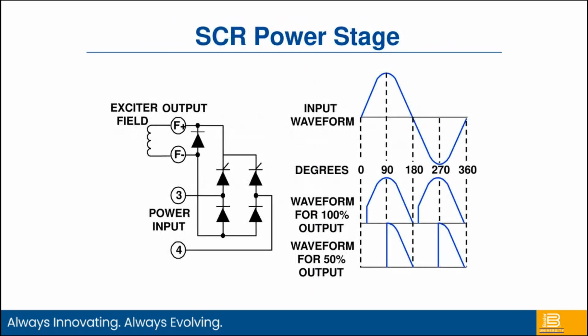So with that, I brought up a point there of power stages. The voltage regulator is monitoring the output of the generator, very much like the cruise control on your car does with speed, except we're doing it with generator voltage. But the power stage is what's actually doing the work. We take that AC signal that's being fed into the voltage regulator and turn it into DC and use that to drive the flux on that rotor, or flux in the field, the magnetism in the field, higher or lower to control our generator voltage.